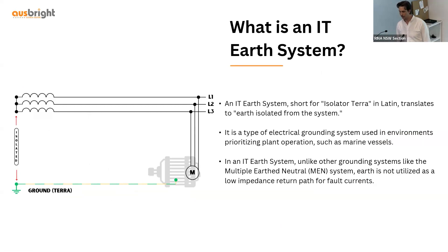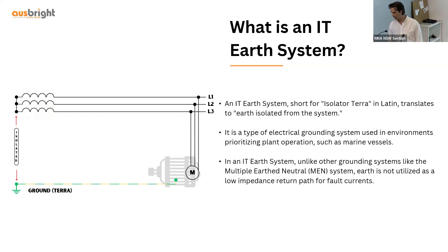What is an IT Earth system? IT stands for isolated terra, which means the system is isolated from ground — there is no connection between the source and ground. It's mainly used in systems or areas that need to prioritise operational plant, which includes marine vessels. Unlike a MEN system, there is no Earth-neutral, so there is no Earth utilized for a low impedance return path for fault currents.